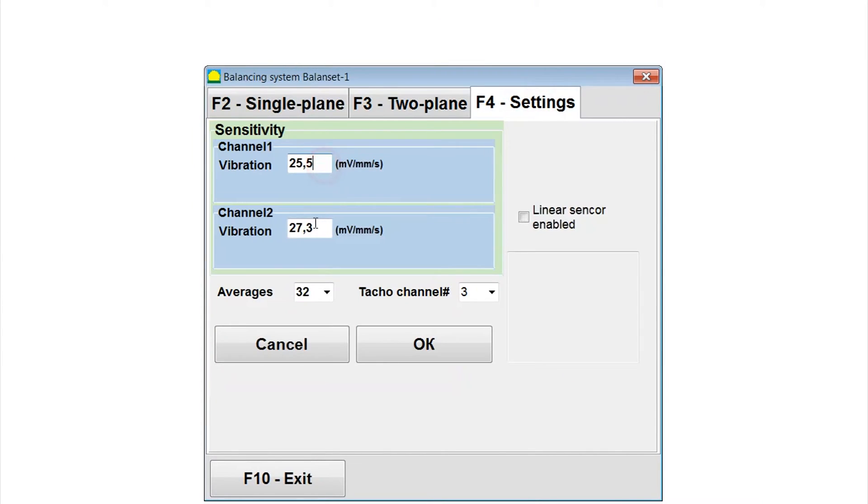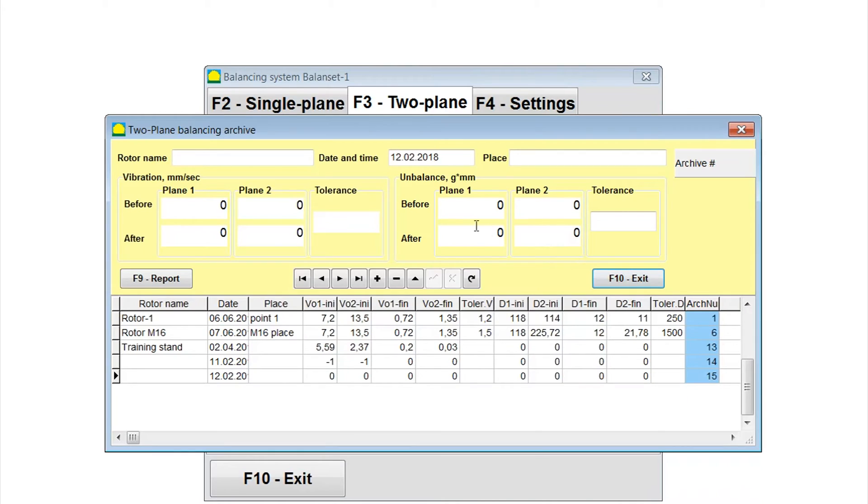Run the Balanset-1 software. In the open software window we see three tabs. Select two-plane and click on the balancing button. Enter the rotor name, type, and place of its installation.